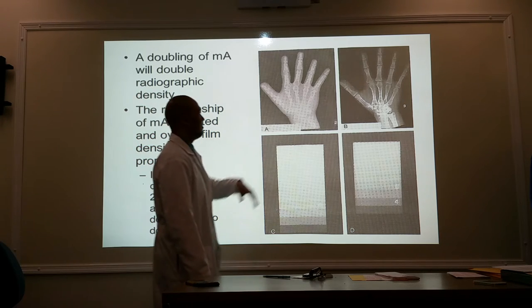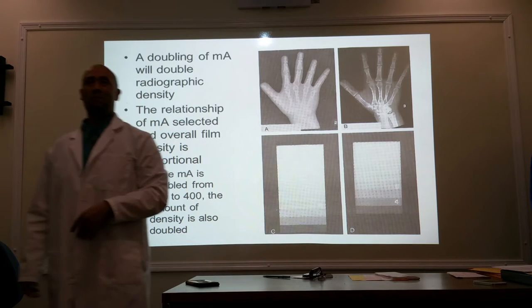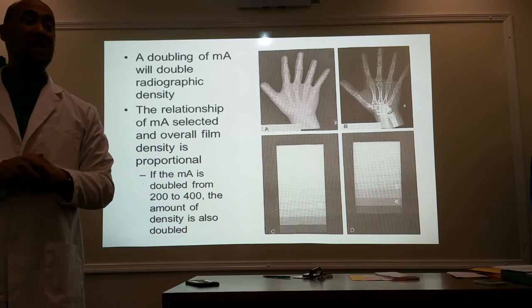Here's the example: 200 MA — too light. Let's go shoot it again. Now it's twice as dark. But you've got to be cautious when manipulating MA or time or MAS as one unit, because when you're manipulating MAS, you're also manipulating patient exposure. If I doubled my MA, I've doubled my patient exposure — because now I've produced twice as many electrons, twice as many x-rays.